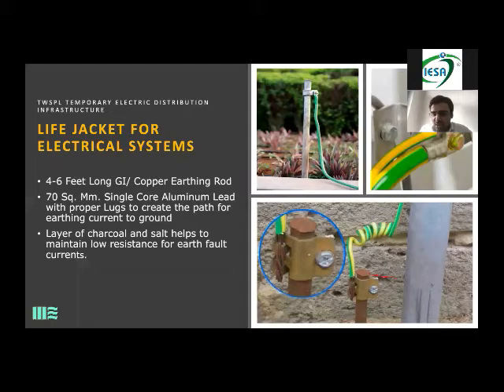So again, for a machinery load, it is definitely preferred that we use pipe earth or maybe chemical earth also. The pipe earth is good for that. Whenever you're nurturing the ground, watering it, putting in coal and salt, it all depends on the load. The higher the load, the better the earthing has to be. I'm talking about a hotel or a small place where only sound and LED lights don't run on a lot of load. But when you have a lot of ACs, huge loads, then it is preferable that you go for the copper earth.